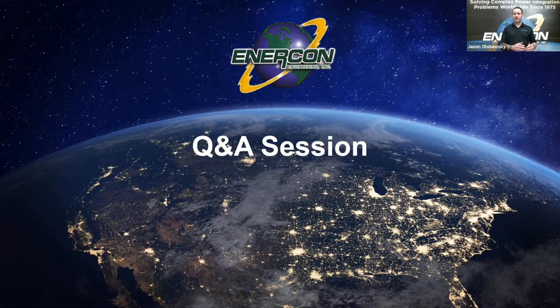Sure. So the switchgear is the first piece of equipment in line, and it's going to contain your utility coming in, and your standby generators would be cabled into the switchgear, and then those first feed into the rest of the plant. But switchgear is also going to contain the intelligent controls and touch screens or visuals gathering other information from the plant. So you're going to see more intelligent controls within the switchgear. Switchboards are mostly just going to be breakers and feeds. So you're not going to see too much instrumentation or controls in that aspect. It's mostly going to be manually operated for the most part and contain thermal mag circuit breakers.